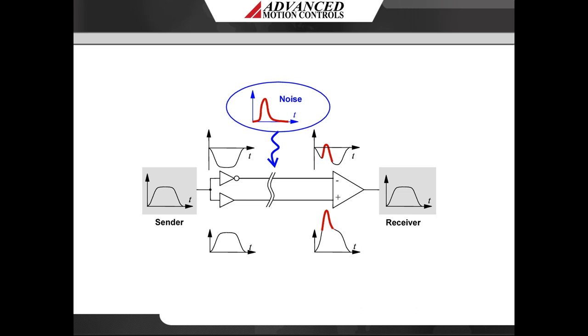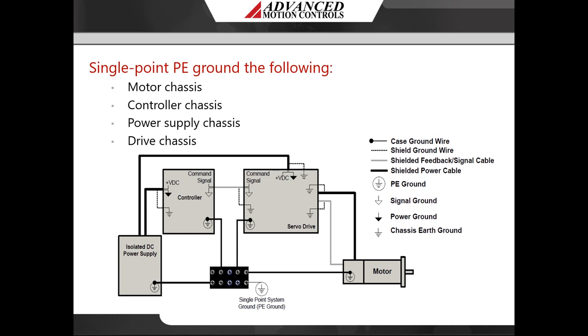Proper grounding is critical to diminish the effects of all noise sources by providing a low impedance path to ground for EMI currents. In most servo systems, the case grounds of all the system components should be connected to a single protective earth ground point in a star configuration. Grounding the case grounds at a central PE ground point through a single low resistance wire reduces the chance for ground loops and helps to minimize high frequency voltage differentials between components. All ground wires must be of a heavy gauge and be as short as possible.